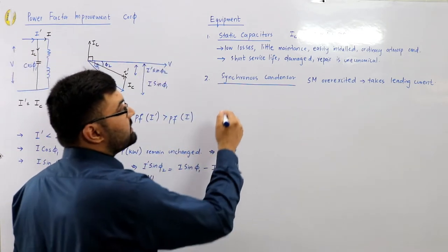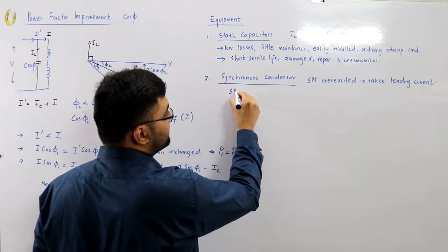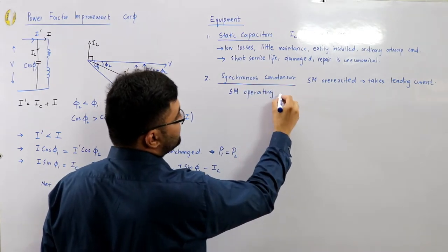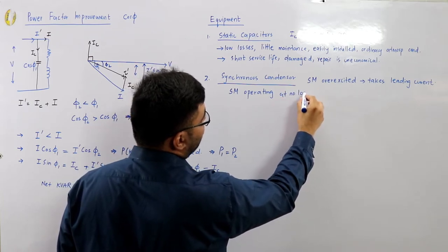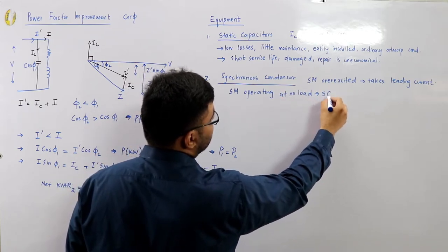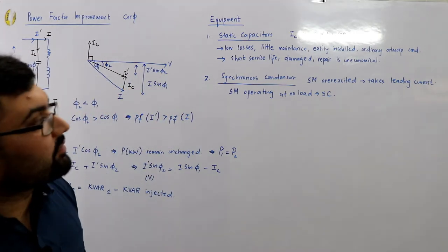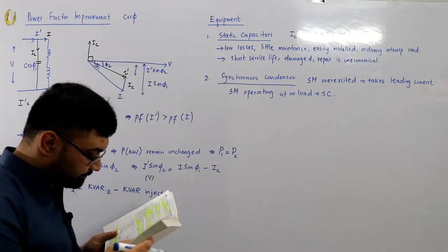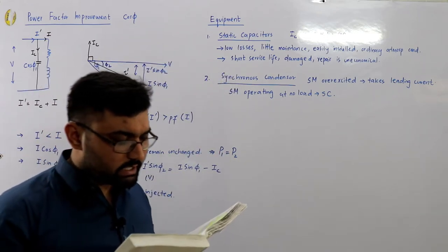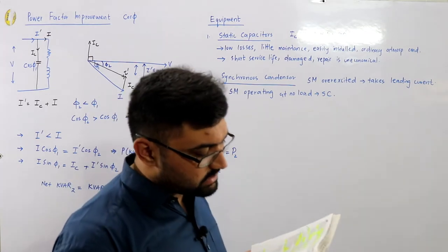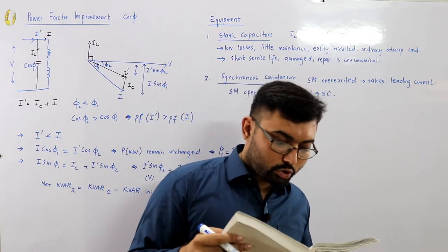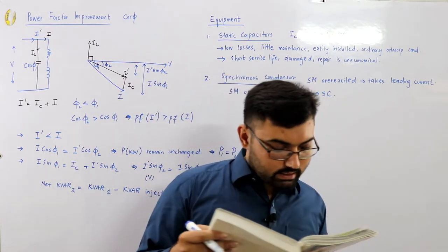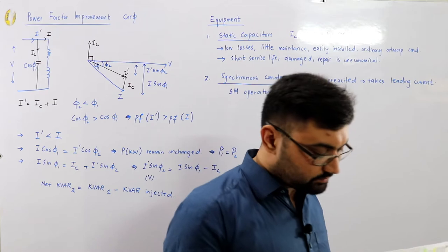And similarly, the synchronous condenser is a synchronous motor operating at no load. This is called a synchronous condenser. So with the help of a synchronous condenser, you can improve your power factor. The idea is the same. A synchronous motor takes leading current when overexcited, therefore it behaves as a capacitor. An overexcited synchronous motor running on no load is known as a synchronous condenser.